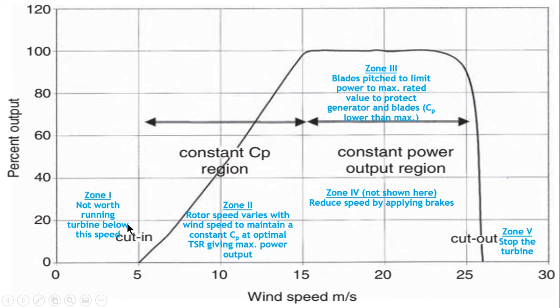In Zone 1, it is not worth running the wind turbine below this speed, and similarly the windmill is stopped after the cut-out speed. Now let's discuss Zone 2, Zone 3, and Zone 4. In Zone 2, the rotor speed varies with respect to wind to maintain a constant rotor efficiency and optimal tip speed ratio. In this area, maximum power is ensured.